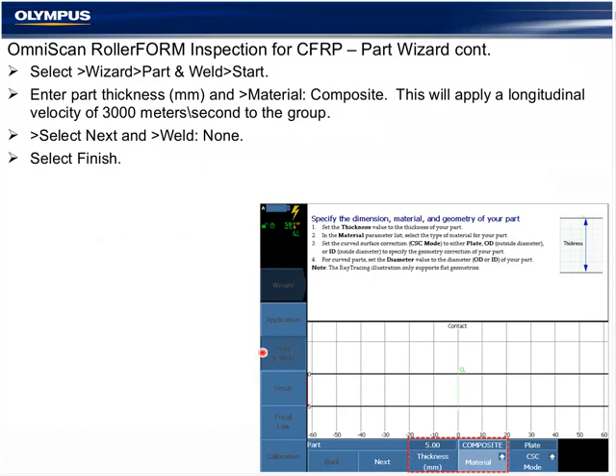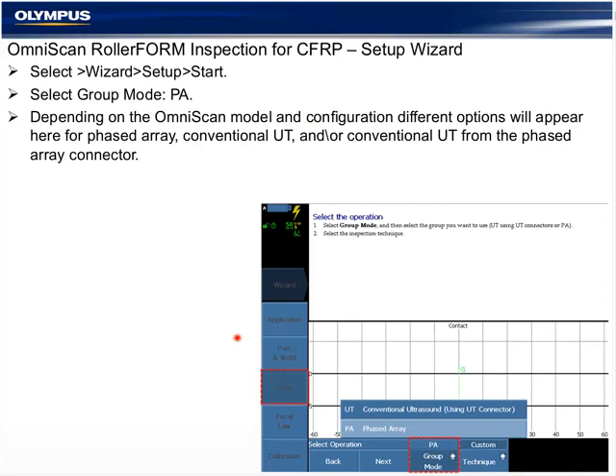On the part wizard, we're going to enter the thickness of the component and select Material Composite. The thickness entered here will have some default value in the color palette and the gate logic, maximum and minimum positions, and selection of the material of composite will associate a longitudinal velocity of 3,000 meters per second with the inspection. Continue in the wizard and select Next, where there's no weld associated with this, and Finish. That will conclude the part wizard, moving to the setup wizard.